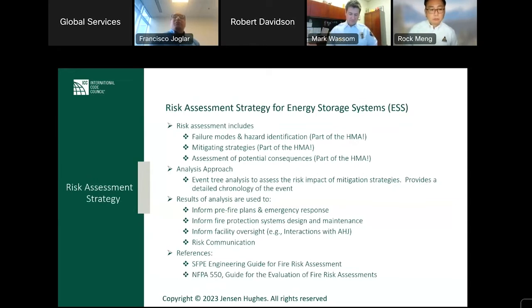If you look at this from the perspective of risk assessment, then every element that I mentioned of the hazard mitigation analysis will be important, right? Failure modes and hazard identification, that's part of the HMA. You have to list what can happen in terms of fire hazards. This case includes explosions. You have to have a very comprehensive list of mitigation, and that starts from housekeeping, fire prevention, right? The battery management system through the response to a fire or explosion. And then what are these consequences?